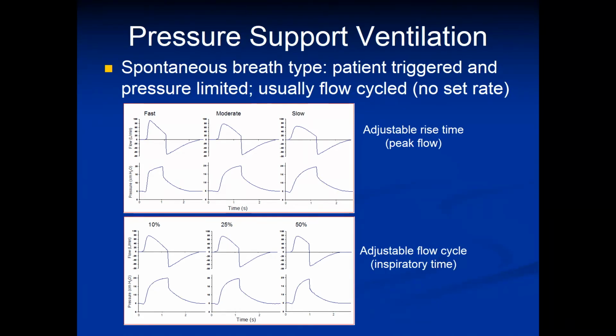Most ventilators usually default that feature to 25% of the peak flow. So once the breath decelerates down to 25% of the peak flow, the ventilator turns off and switches into the expiratory phase. But this can be adjusted. We may want to adjust this down to 10% in a patient that perhaps we want to try to capture a little additional tidal volume, or we may want to adjust it higher to, say, the 50% setting for patients with chronic obstructive pulmonary disease. And by doing this, this will shorten their inspiratory time and allow for more time for their lungs to empty.